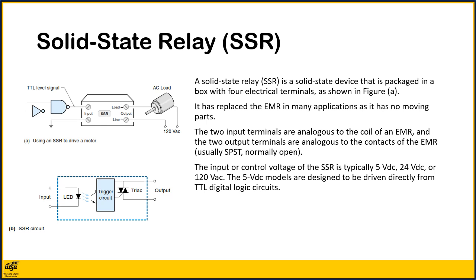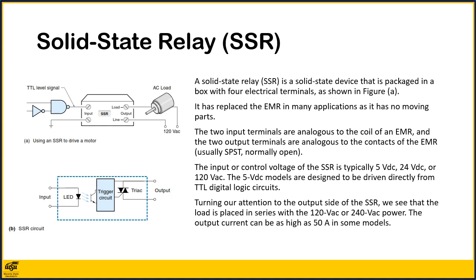The input or control voltage to the SSR is typically 5 volts DC, 24 volts DC, or 120 volts AC. The 5 volt DC models are designed to be driven directly from TTL digital logic circuits. Turning our attention to the output side of the SSR, we see that the load is placed in series with the 120 volt AC or 240 volt AC power. The output current can be as high as 50 amps in some models.